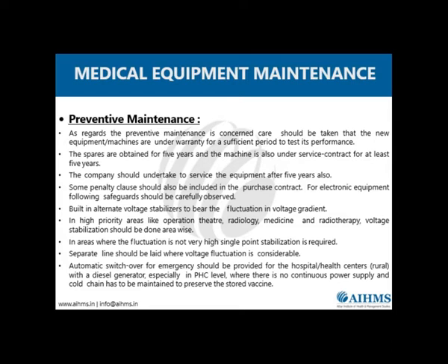And then there should also be an arrangement for alternate voltage stabilizers, and in high priority areas like the operation theater, radiology, medicine, and radiotherapy, the stabilization is of immense importance, otherwise it can damage the machine fully.